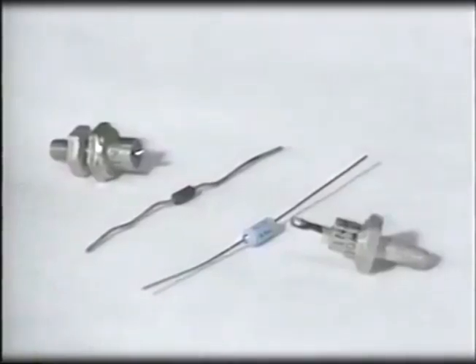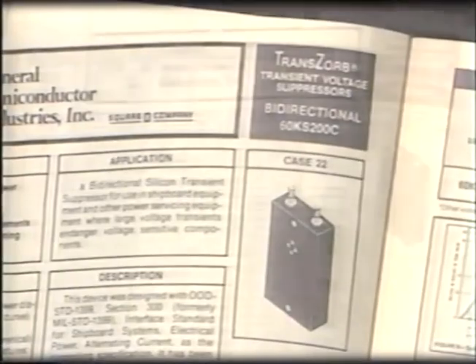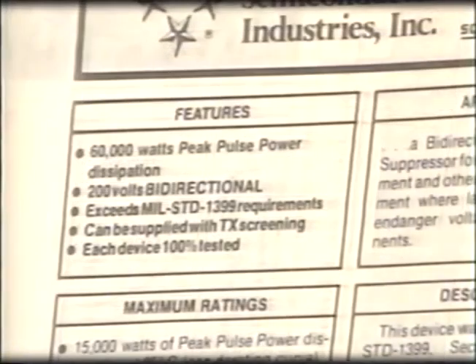Other devices are also used as transient protectors. By themselves, silicon avalanche suppressors and Zener diodes offer fast response time, but only unipolar protection. Packages are available that incorporate silicon avalanche suppressors, Zener diodes to offer bipolar protection.